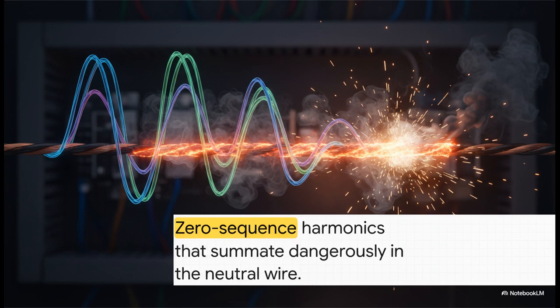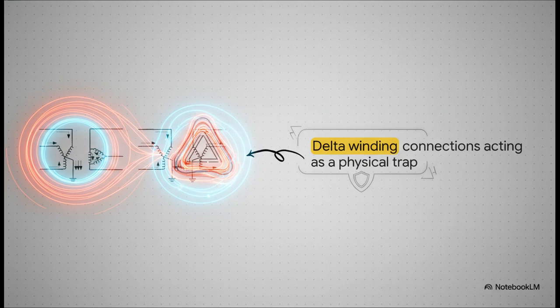Instead, they summate. They add together entirely, flowing directly into the neutral wire of the system, causing immense overheating and major fire risks. But this is where the engineering gets brilliant. Check out the triangle or delta-shaped winding connection here. This delta transformer acts as an ingenious physical trap for those triplen harmonics. Because of the way the copper coils are wired in a continuous loop, those dangerous zero-sequence harmonics go into the triangle and they get stuck.